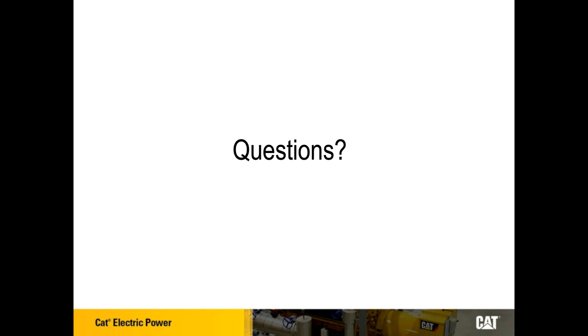Bailey, a point of clarity one of our audience members asked regarding gas generator sets: is the 2,000 kW the largest gas gen set CAT makes? It's actually not the largest. We also offer a 2.5 megawatt, a 3 megawatt, a 4 megawatt, and even a 6.5 megawatt and a 10 megawatt generator set. But for a standby application, the 2 megawatt is the largest that's really suitable. The larger sizes are optimized for high run hour, continuous, or prime applications, meant to run economically for long periods rather than start quickly for short periods. So we do make bigger ones up to 10 megawatts, but for standby applications, 2 or 2.5 megawatts are the largest that are practical.